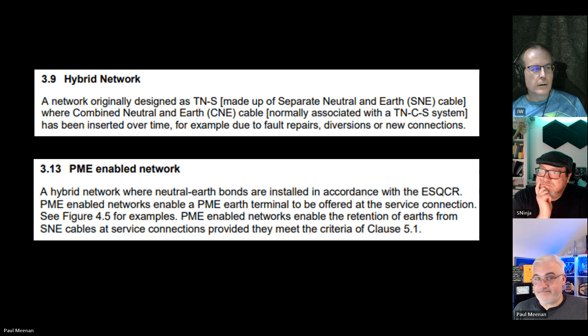So 3.13, and it's well worth getting a copy of it. I'll probably put the link in the YouTube video as well. PME-enabled network is defined as a hybrid network where neutral earth bonds are installed in accordance with ESQCR. Yeah, right. PME-enabled networks enable a PME earth terminal to be offered at the service connection, see figure 4.5 for example. PME-enabled networks enable the retention of earths from SNE cables at service connections, provided they meet the criteria. So that kind of explains these Frankenstein cutouts where they leave the TNS connections. It's a PME-enabled network, and that's what that clause tells you.